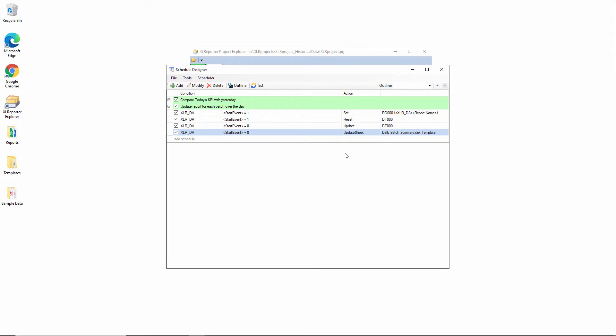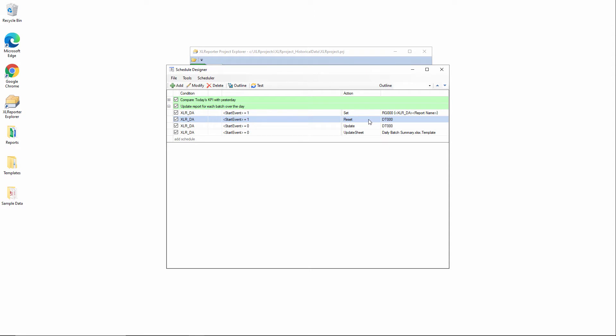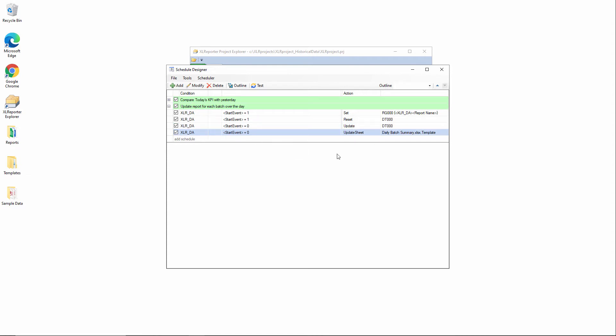We need to keep track of the ID of the batch or the cycle that each row represents. We need to keep track of the start time of these batches or events, the end time of each. And then once we have all that requisite information, then also at the end of the batch, the report can be updated. So in order to complete this schedule, we have to fill in the start event and report name parameters.